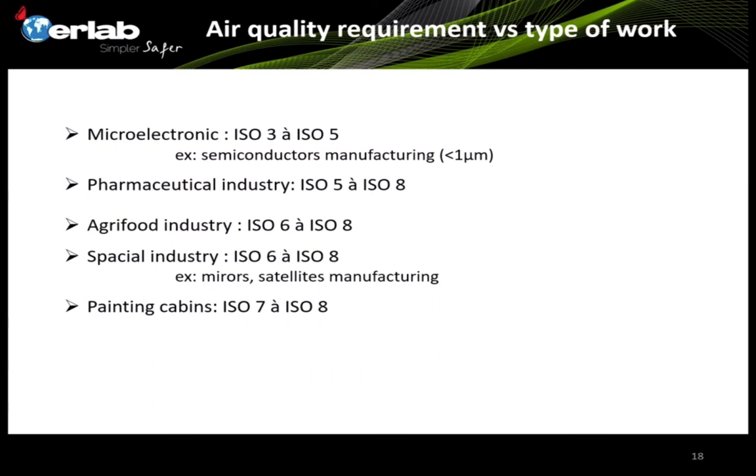The most commonly requested air cleanliness for PCR — which is also the same for BSC internal environments — is ISO 5. ISO 5 is also what is most commonly used in pharmaceutical industry and surgery rooms. For better cleanliness, you find higher classes used in microelectronics, which is very sensitive to dust. Lower cleanliness classes are found in agri-food industry, space industries, or painting cabins.